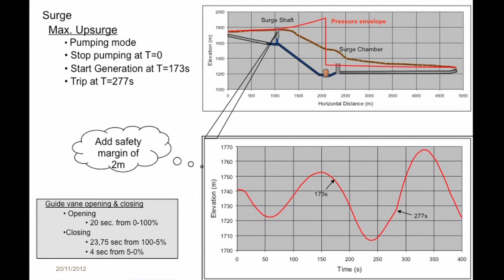You are pumping, that's at time 0, still pumping. This is the level of the surge, of the water level in the surge shaft. Now you stop pumping. Immediately you stop that column of water. You stop that, but this is still carrying on. So it sucks actually water from the surge shaft, and the surge level drops. Suddenly now you put motion into the surge. So if you put motion downwards, it will go upward again. And then at that point, just when it wants to go down, national control tells you, right, start generation.